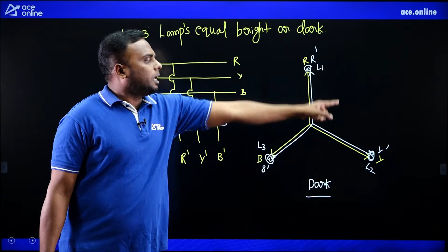Once all the lamps are dark or all the lamps are bright, we can say both are at same frequency and same phase sequence. If phase sequence is different, lamps will not show equal bright, equal dark together. They will show one dark, remaining 2 brighter. If phase sequence is different, you will never get that condition. You get this only when the two systems have same sequence and same frequency.